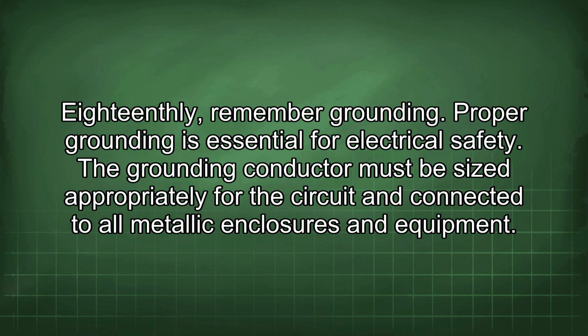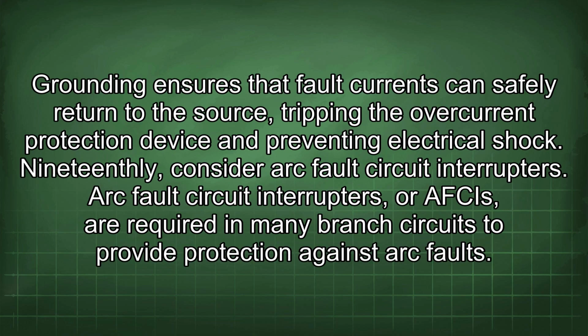18thly, remember grounding. Proper grounding is essential for electrical safety. The grounding conductor must be sized appropriately for the circuit and connected to all metallic enclosures and equipment. Grounding ensures that fault currents can safely return to the source, tripping the overcurrent protection device and preventing electrical shock.